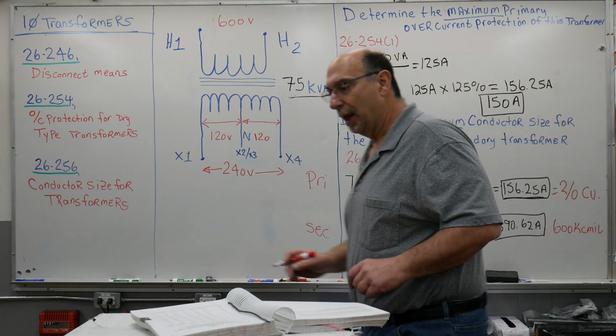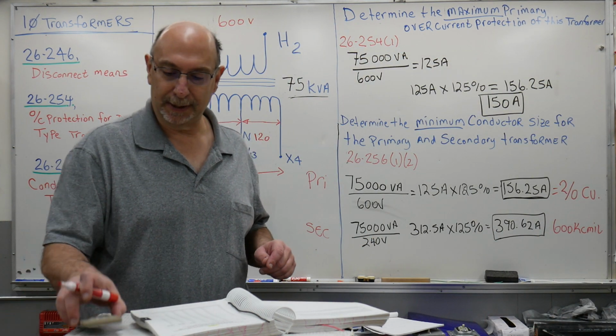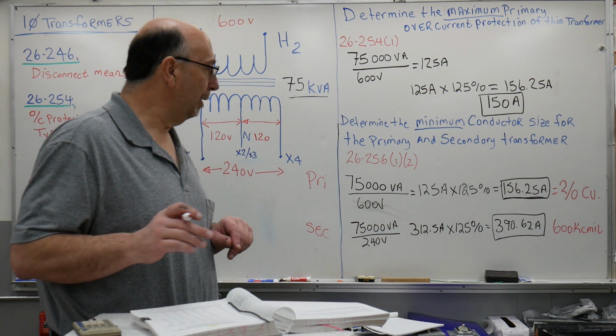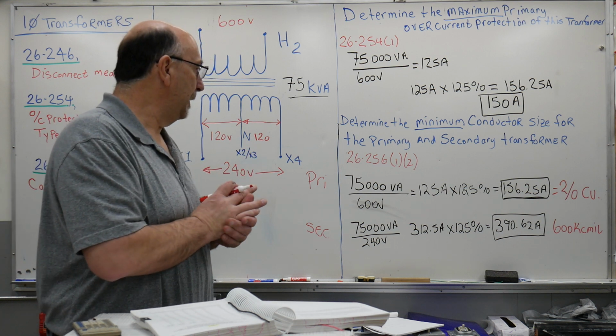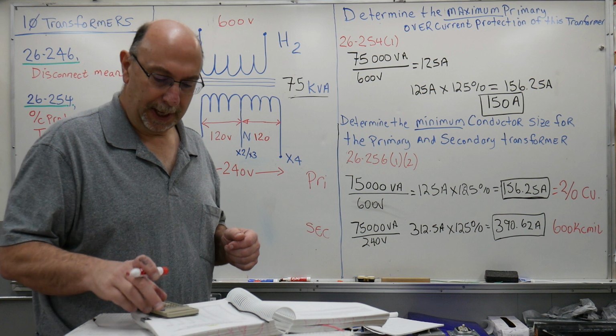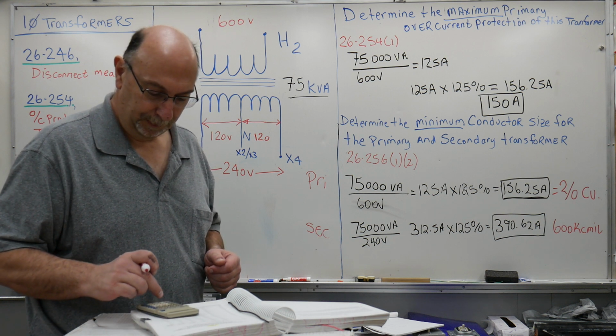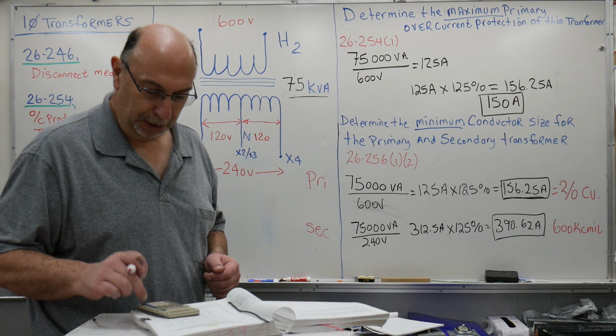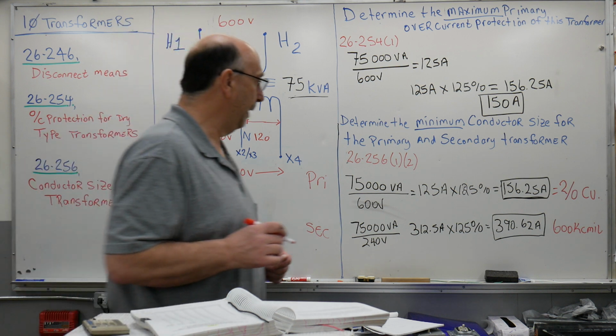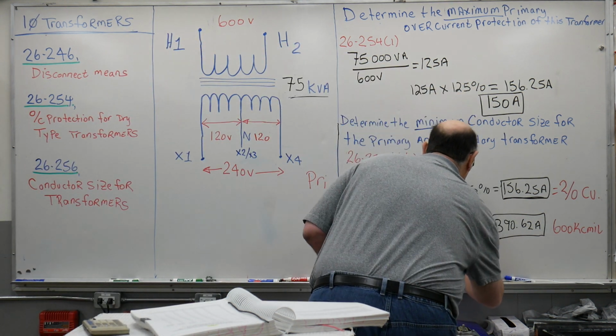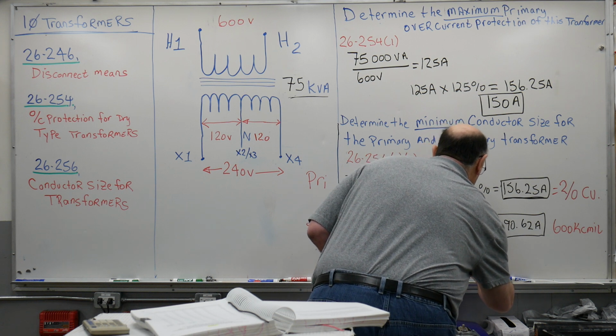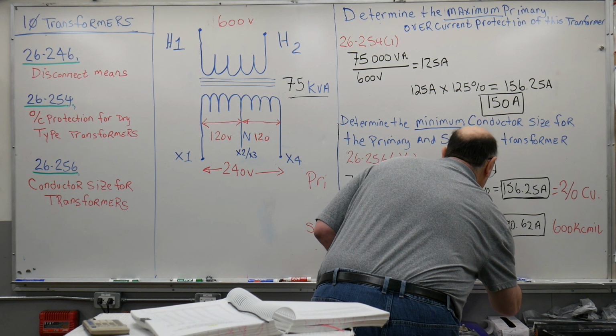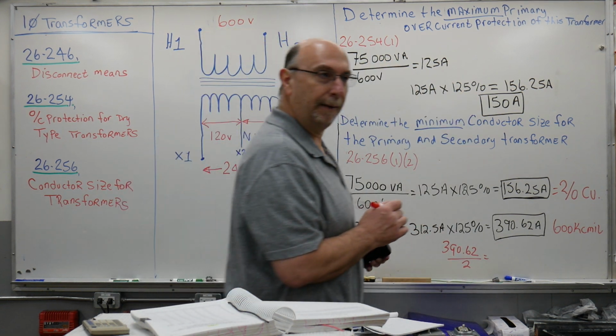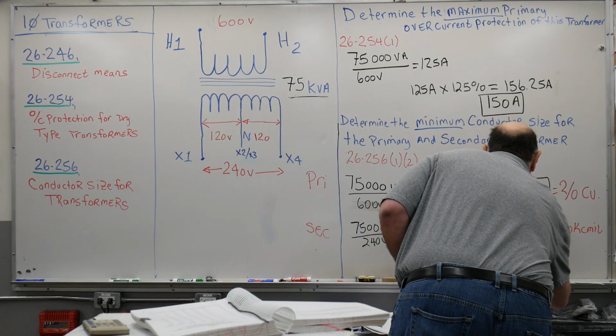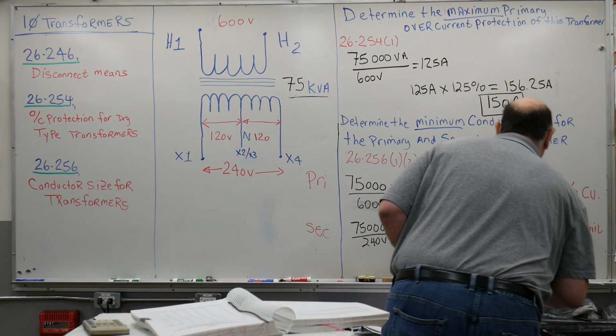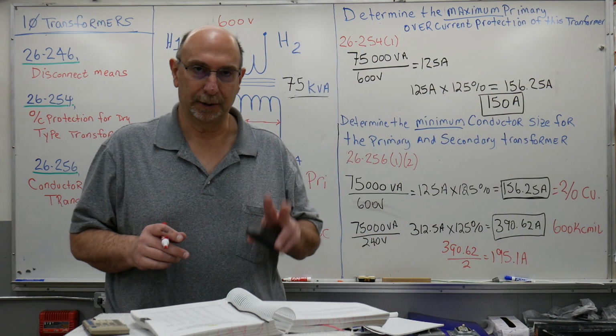Now, a lot of times it's pretty tough to get 600 kcmil, so we run parallel runs. So in this case, let's take our 390.62 and we're going to divide it by 2. Okay? And what do we come up with? 195.1? So we're going to run parallel conductors, so 2 runs.